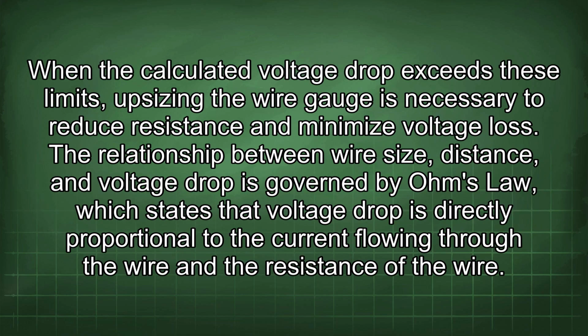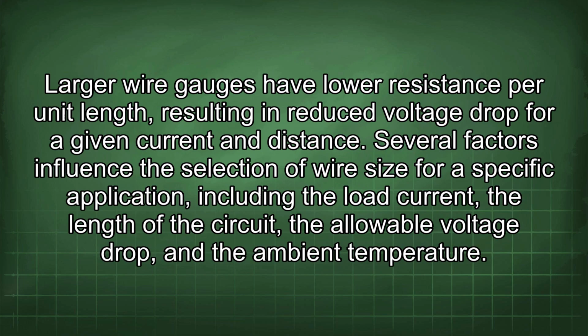When the calculated voltage drop exceeds these limits, upsizing the wire gauge is necessary to reduce resistance and minimize voltage loss. The relationship between wire size, distance, and voltage drop is governed by Ohm's law, which states that voltage drop is directly proportional to the current flowing through the wire and the resistance of the wire. Larger wire gauges have lower resistance per unit length, resulting in reduced voltage drop for a given current and distance.